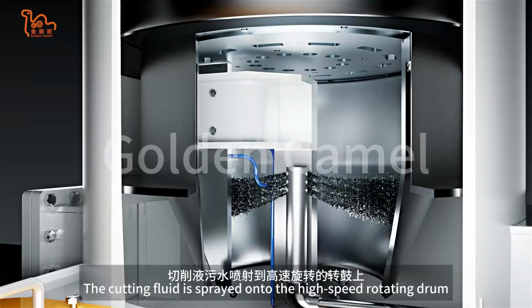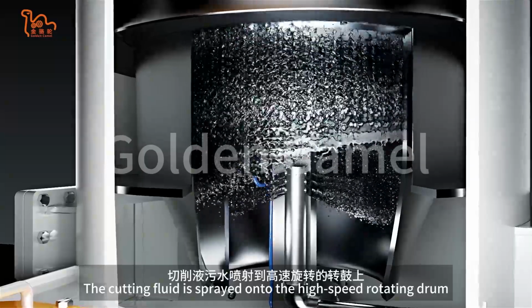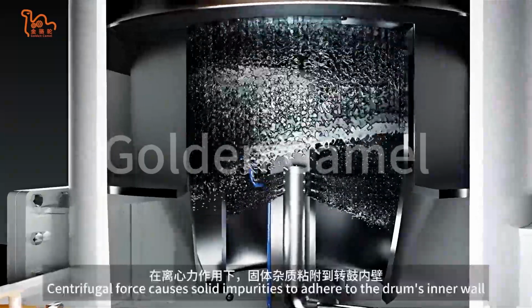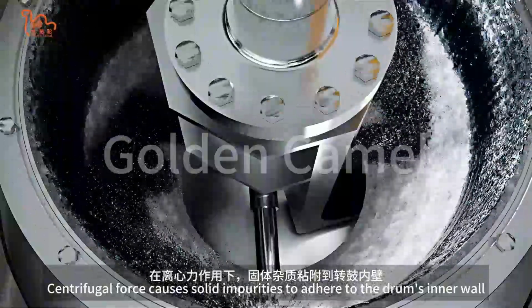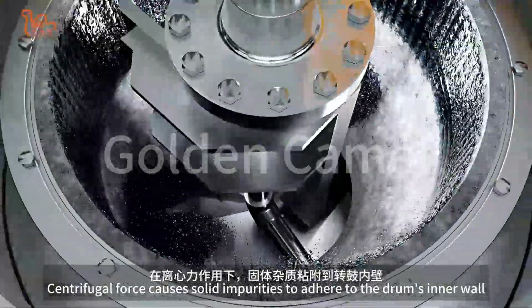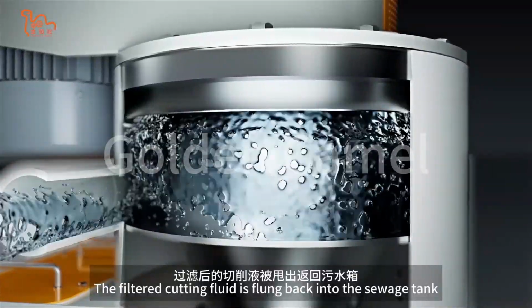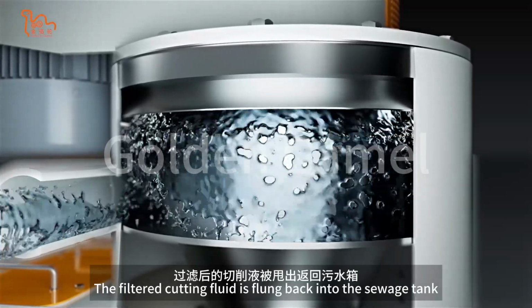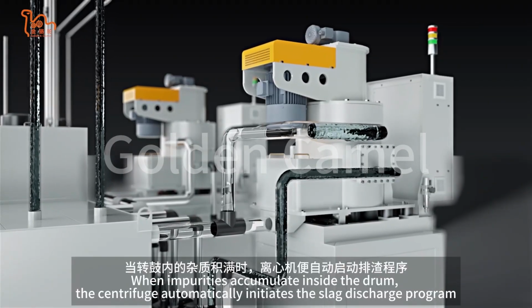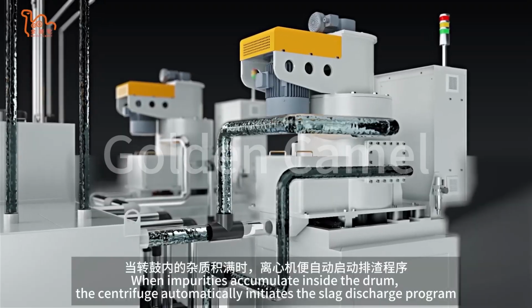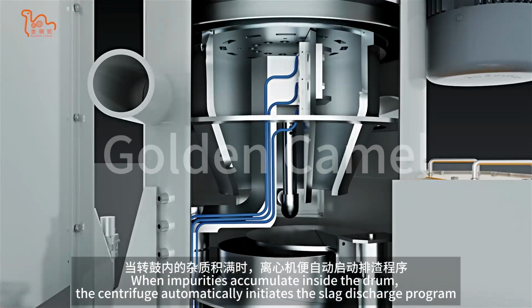The cutting fluid is sprayed onto the high-speed rotating drum. Centrifugal force causes solid impurities to adhere to the drum's inner wall. The filtered cutting fluid is flung back into the sewage tank. When impurities accumulate inside the drum, the centrifuge automatically initiates the slag discharge program.